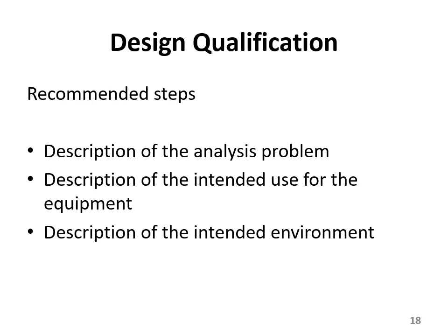There are a few steps which, if you are following while doing the design qualification, help you a lot, right? What is helpful is to just describe the analysis problem. If you're getting some problem, describe it. Describe the intended use of the equipment. If you are using an equipment, what is the intended use? Design it properly. What is the intended environment? So describe the intended environment, the environment where you're going to use the machine. That is also important. Describe it.